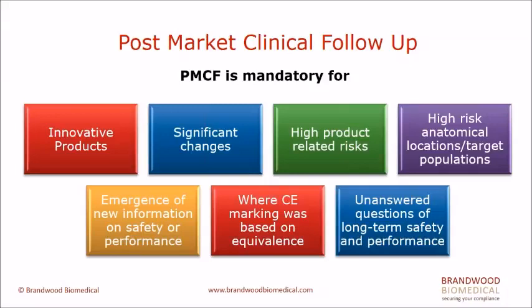If your original clinical evaluation report was not based on direct clinical trial data, it was based on an equivalence argument, and a lot of clinical evaluations are done that way, where you don't do a direct clinical trial, but you create a report with a comparison to a predicate device and say, this predicate device is well established and my device is the same, therefore I don't need to do a clinical trial. Well, the regulations say that's fine, you can do that, but you must now follow that device in the post-market to confirm that indeed it is the same as the predicate, that it does perform adequately.